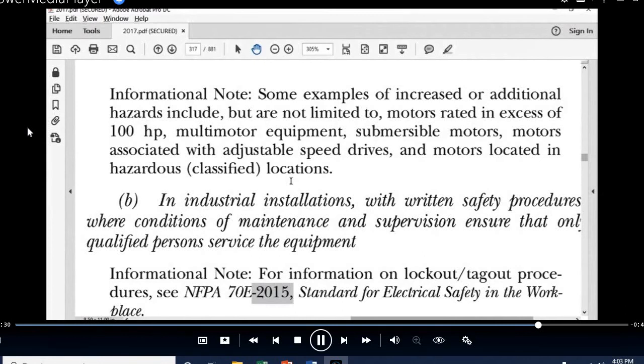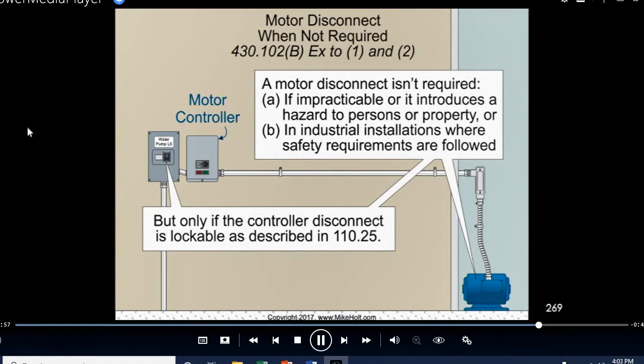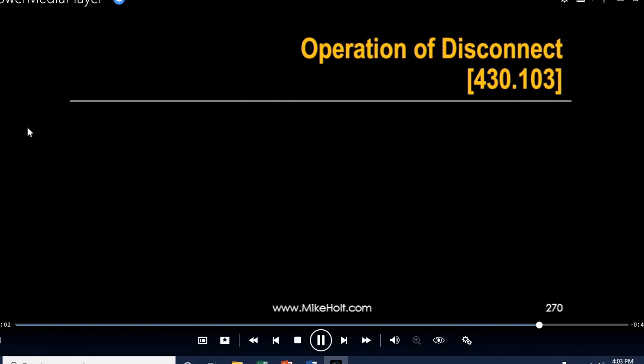Eric? Yeah, sometimes even if the code doesn't require a disconnect by a motor, you see them anyway when the controller or the source is out of sight, simply for the zero voltage checks. When an electrician goes out there to work on it, you have to do a zero voltage check to verify that the circuit is de-energized. It's easier to open up a disconnect and do that than it is to open up the motor connection box. Okay. All right. Very limited application. So you're going to have one inside of the controller. You're going to have one inside of the motor. Now let's talk about where you have to locate them.